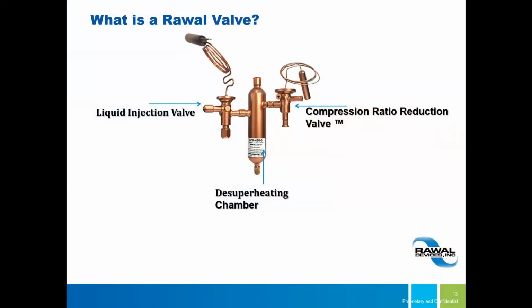So what is a Rawal valve? The idea is that it's a pressure control device that allows you to manage situations where you're trying to trick a compressor into managing the load better, instead of just doing hot gas bypass. You've got a liquid valve, with your liquid line coming in here. You've got your desuperheating chamber here, and then there's a compression ratio valve over here, and that's all the components of a Rawal valve. So go to the next slide.